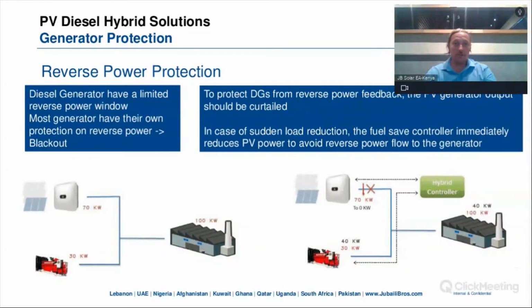So now reverse power protection. This is another function of the fuel save controller. We do not want power from the solar energy to go backwards into the diesel generator. Now, most diesel generators have built-in protection for this, but it will just shut down. That is their protection that's built in. It will shut down the diesel generator, and then you have no power to your load.